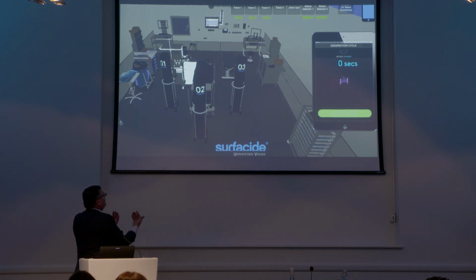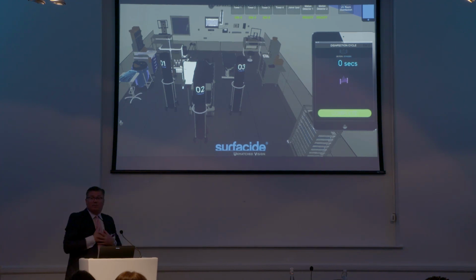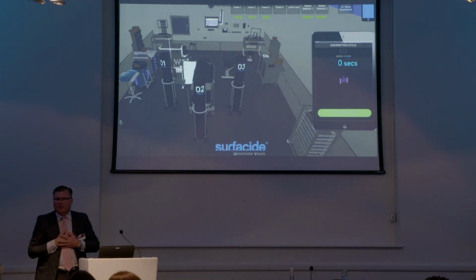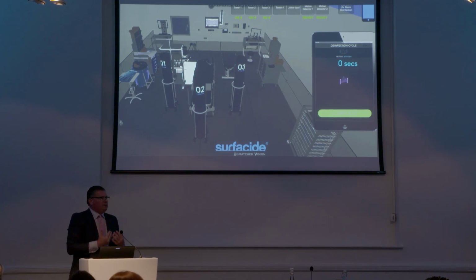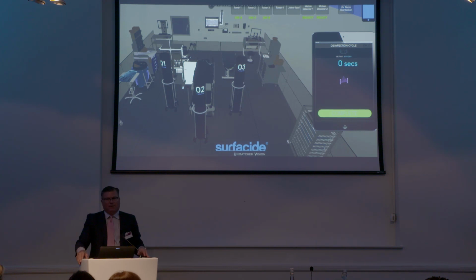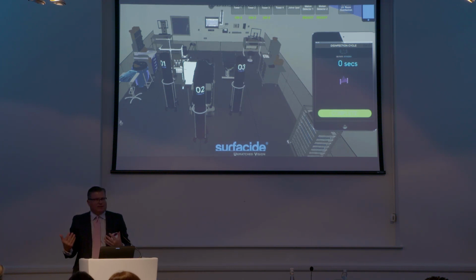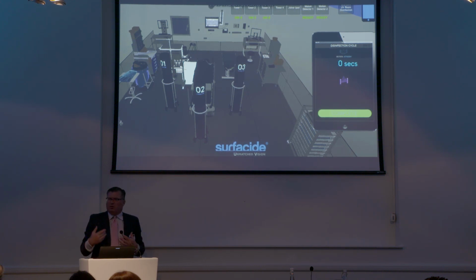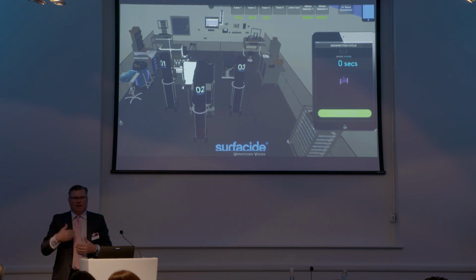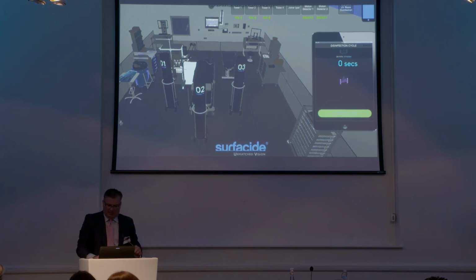If we were oriented here and that was a live system, we would be safe. There would be no radiation exposure to the rear or to the staff because all the energy is being focused forward. Very quick 7-minute cycle, 2 to 3 minute setup time, so we can do turnovers in about 10 additional or incremental minutes as an adjunct to manual cleaning.